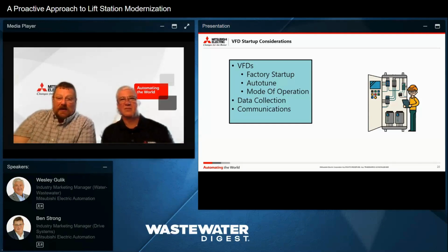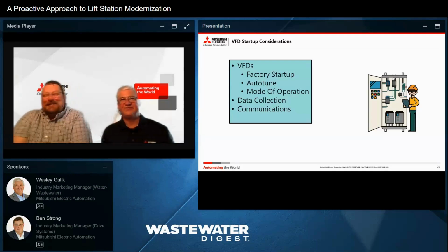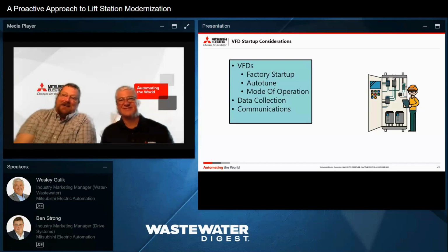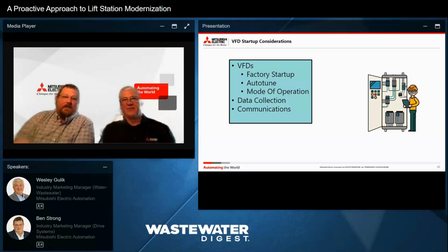but are needed to make informed decisions about how your lift station and your collection systems are operating. And communications: how am I going to communicate? Is it going to be over wireless? Is it going to be 900 megahertz? The lift stations in my neighborhoods, it's a very steep neighborhood, so they have to deal with trees. They have to get line of sight for their radios because they're using 900 megahertz radios going back to a water tower. So those are things we all have to consider when we're upgrading our lift stations.